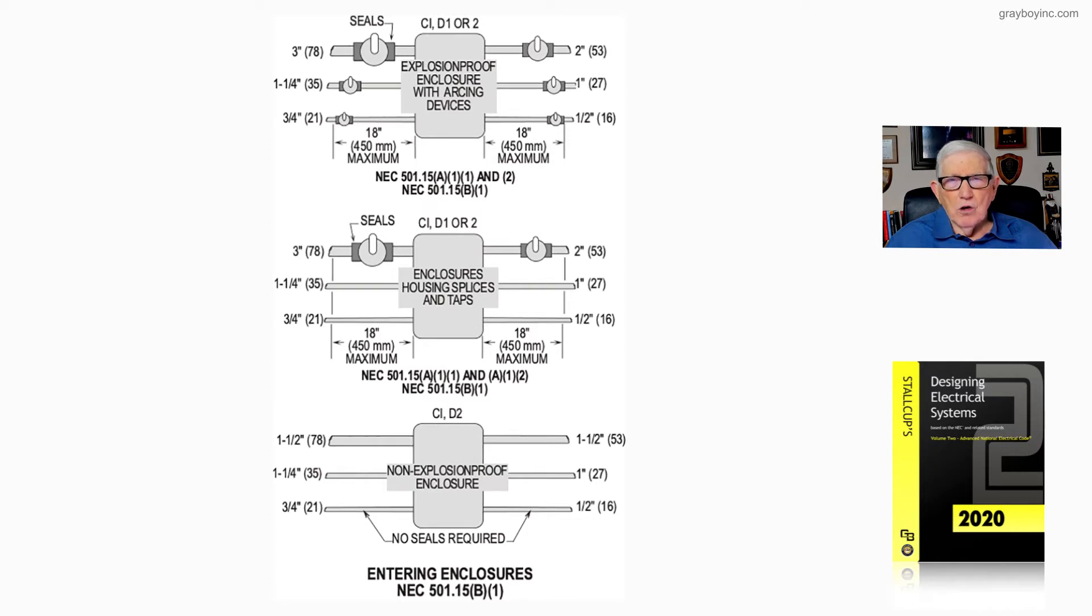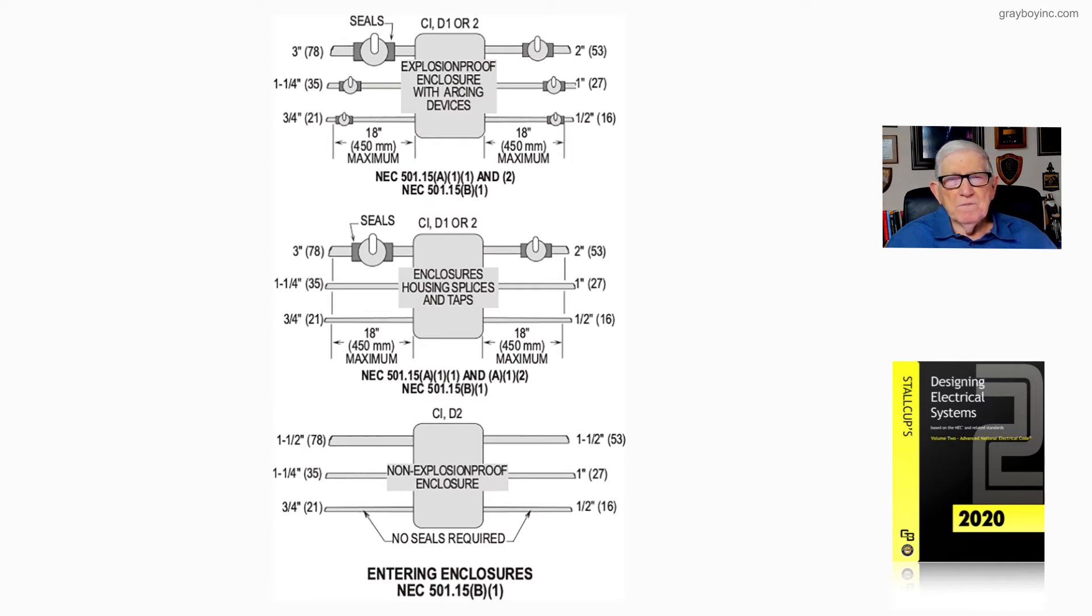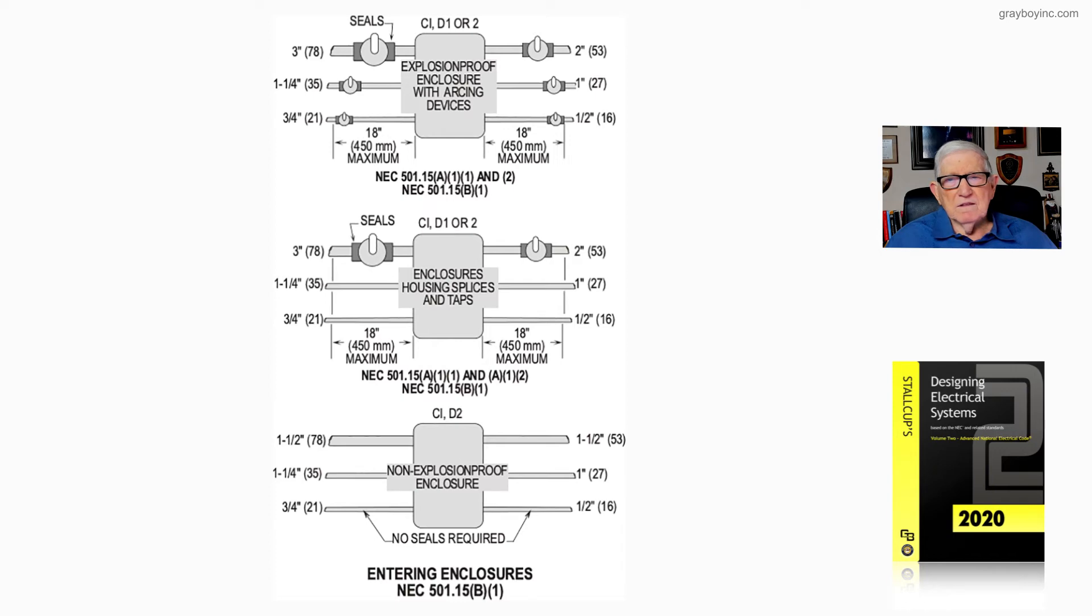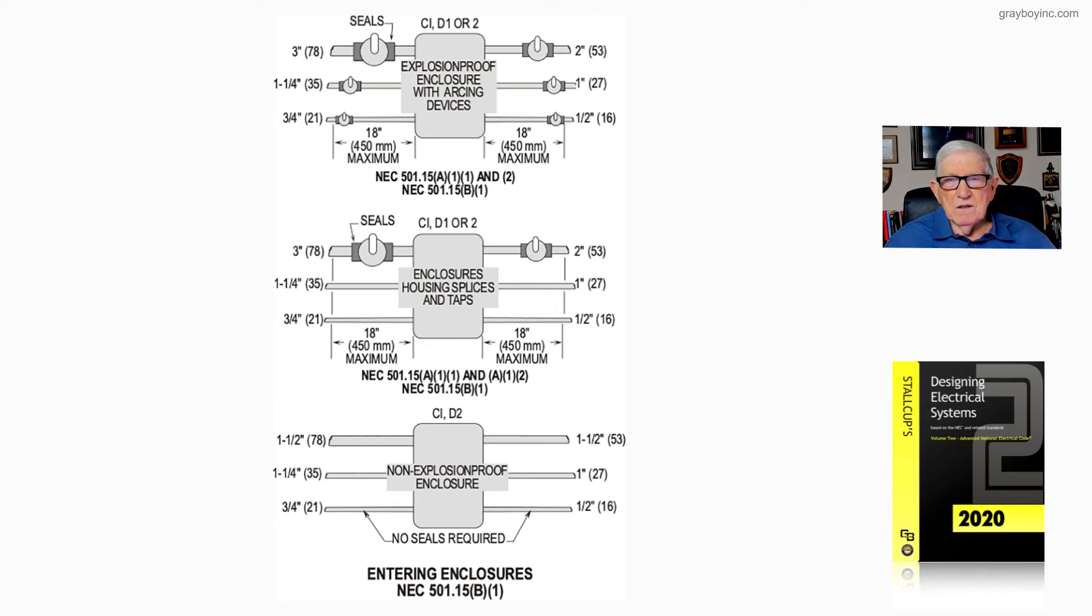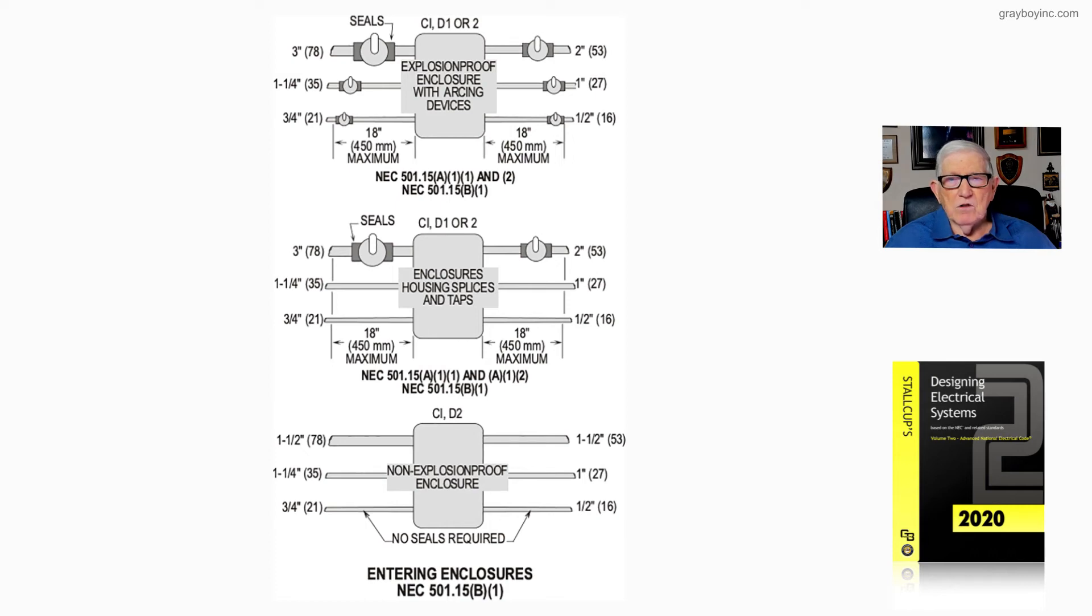Any raceway system or conduit system permitted to be used as a wiring method in this division—notice you don't have to seal like an inch and a quarter, one inch, half inch, three quarters as you see in the illustration. But you're going to have to have that sealing means within 18 inches if it's 2 inches or larger.